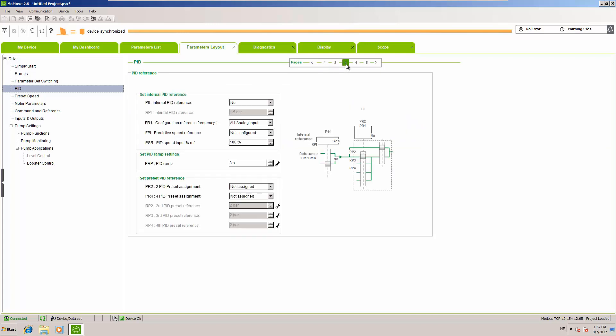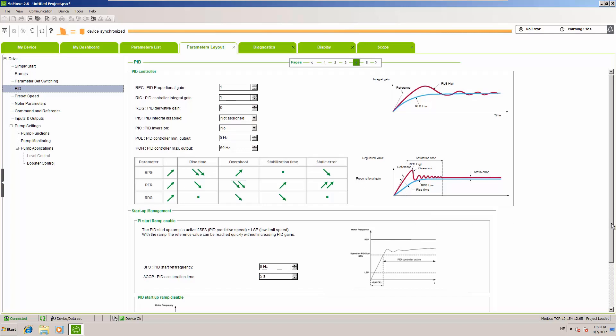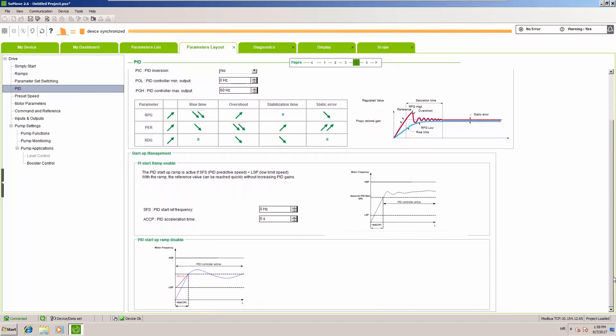On step four, we will not touch the PID gains — we leave proportional gain, integral gain as-is, and derivative is disabled. What we will set up is the PID start frequency to avoid the instability area. We set this to the minimum running speed of our pump, which is 25 Hz. Up to 25 Hz we will have linear acceleration from 0 to 25 Hz according to a 5-second ramp time.